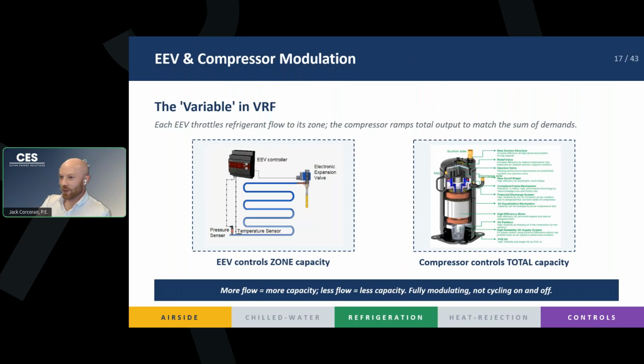So what makes VRF variable refrigerant flow? And what differentiates it from any other piece of equipment that uses the refrigeration cycle in the air side loop? The powerful components are our expansion valve and our variable compressors. EEV is electronic expansion valve. You can see it on the left side in the picture. This device is where we're reducing our pressure in order to get the right cold temperature at our indoor units. Every indoor unit has an EEV. And when the thermostat in the room is calling for lots of cooling or lots of heating, that valve is wide open. It's trying to get as much refrigerant into the coil as possible so that you can evaporate your refrigerant and get lots of heat transfer.